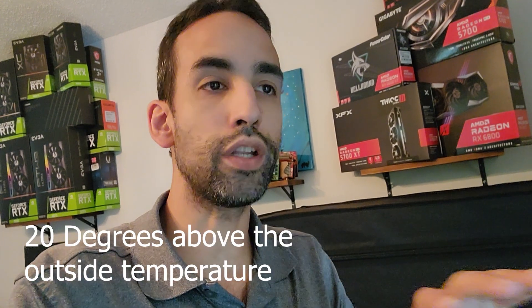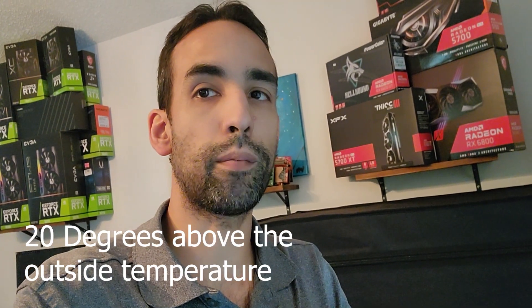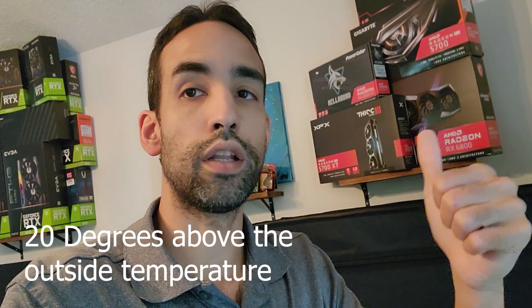The biggest concern is that it's not summer yet. As summer comes, attic temperatures are going to be hotter because outside air temperatures will be higher. Right now inside the house it's about 79 to 80 degrees — the AC just kicked on. You really want your attic temperature to be about 20, maybe 25 degrees at max above outside ambient. The actual outside air is only 76 degrees and our house is three degrees warmer, so we're already stressing that range.